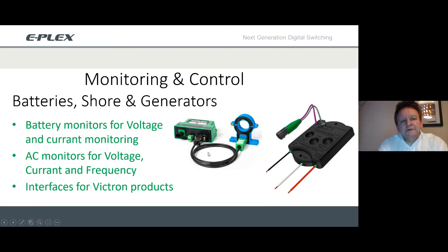We can also do monitoring and control of batteries, shore power and generators - current monitoring, voltage monitoring, and frequency monitoring on the AC side. That information goes onto the network, and you can inhibit control if you want. If you're getting low on power, you can decide whether to use certain power or not, and combine that into the output modules.